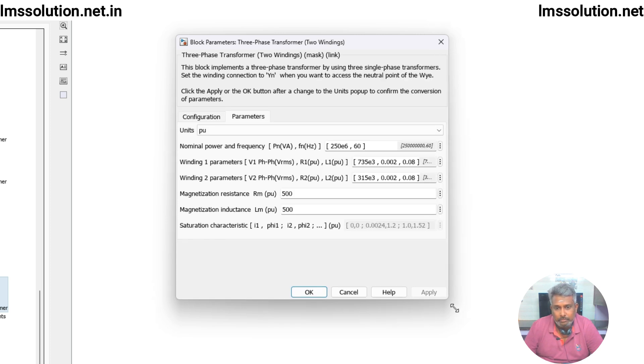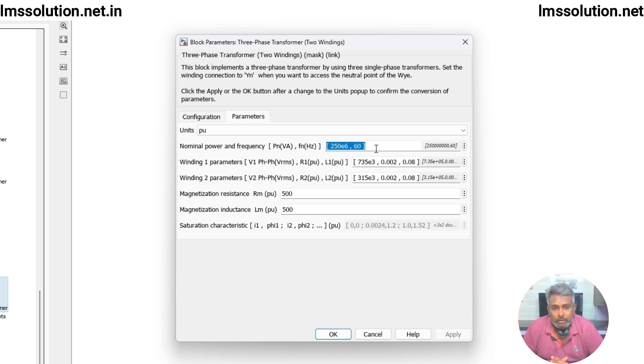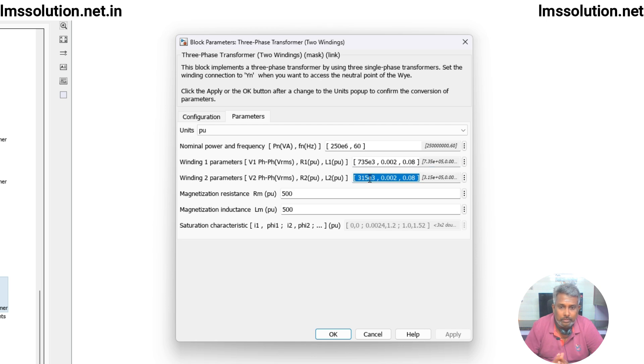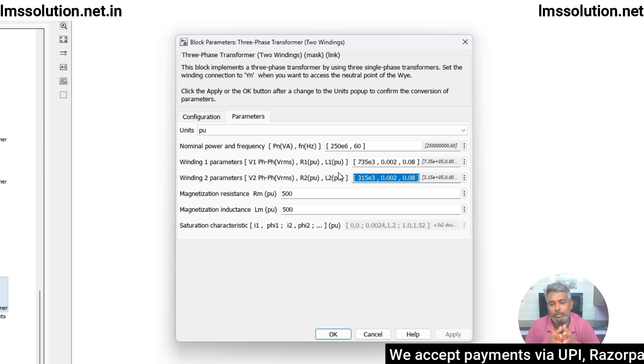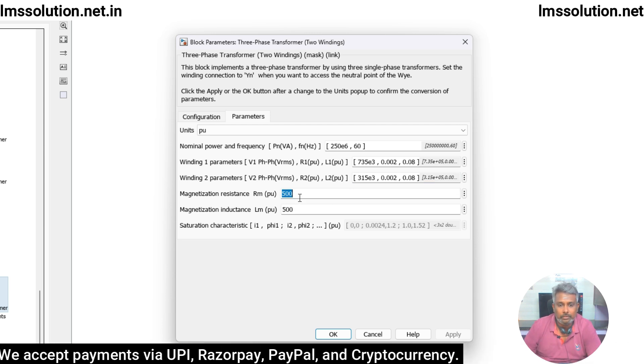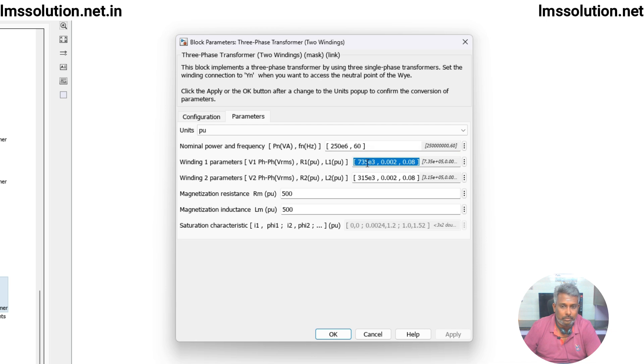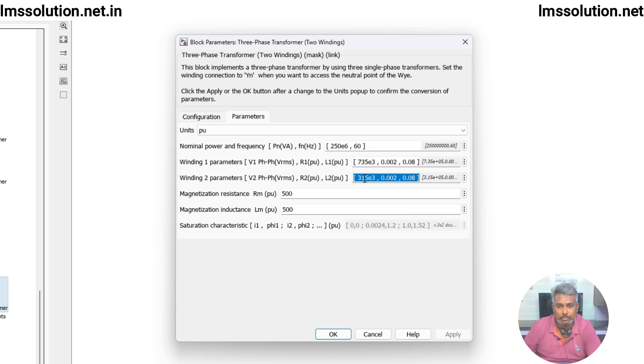Next you can fix the parameters of the power transformer. The first parameter is the nominal power and frequency of the transformer, then winding one details. Here I am fixing the primary voltage at 735 kilovolts, then the R1 and L1 values. The secondary voltage in winding 2 is 315 kilovolts, configured as step-down. You also set magnetization resistance and magnetization parameters.